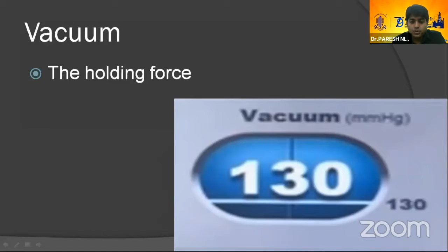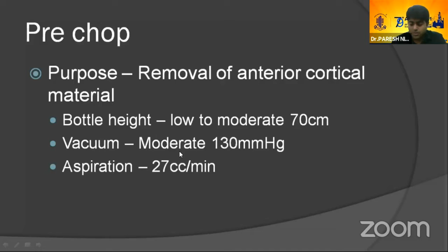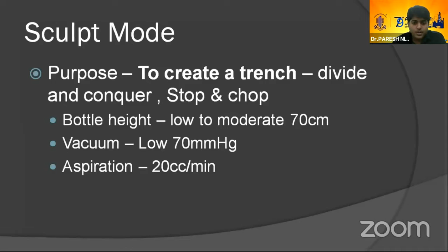Now, depending on the different stages of the surgery, we should modulate the settings. Like in pre-chop mode, our aim is removal of the anterior loose cortical material. The bottle height should be low. Aspiration should be around 27 cc per minute or low, and vacuum should be moderate. In sculpt mode, our aim is to create a trench in divide and conquer or stop and chop. So we don't need much of a holding force. So all the parameters should be kept low.